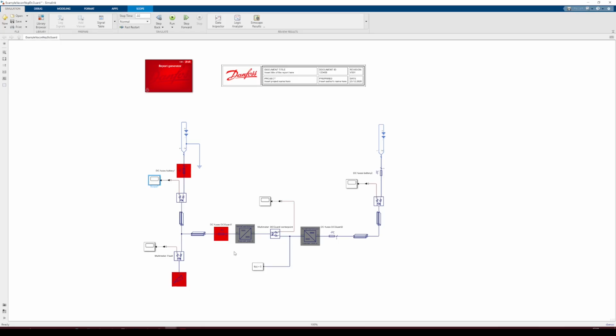So due to the arrangement of the circuit, we have the DC card here in the middle, which then isolates the left and right hand sides of the circuit with the individual batteries. But here on the left hand side, we expect that this fuse at least would burn due to the location of the fault. So only device capable of interrupting the current is this fuse here.